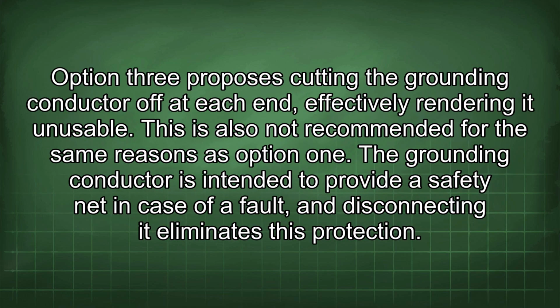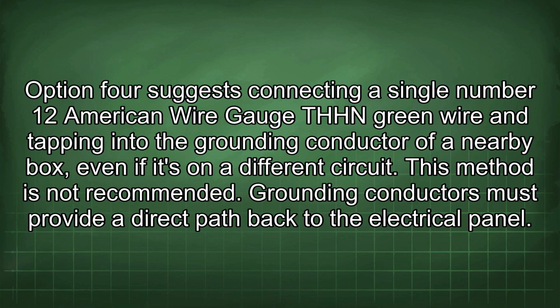Option 3 proposes cutting the grounding conductor off at each end, effectively rendering it unusable. This is also not recommended for the same reasons as option 1. The grounding conductor is intended to provide a safety net in case of a fault, and disconnecting it eliminates this protection.